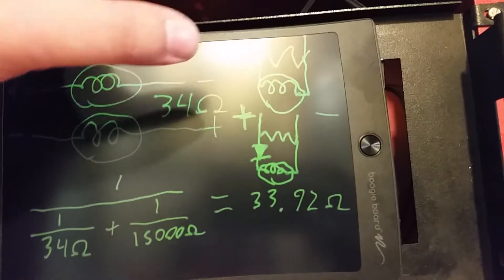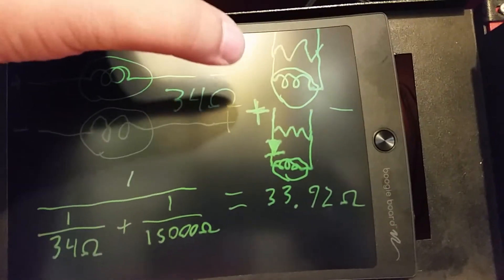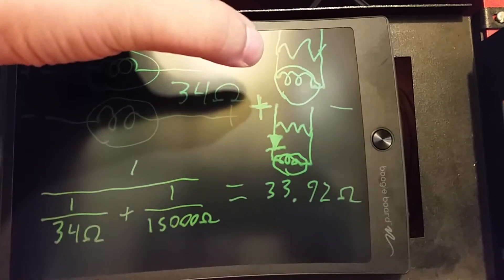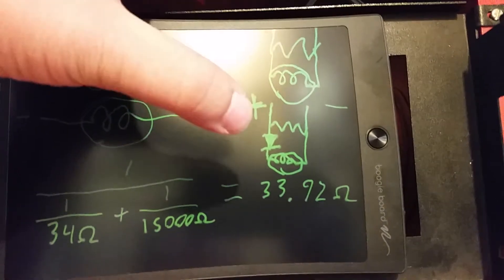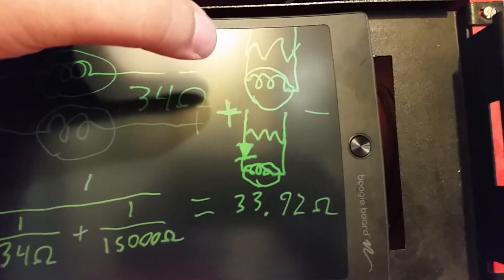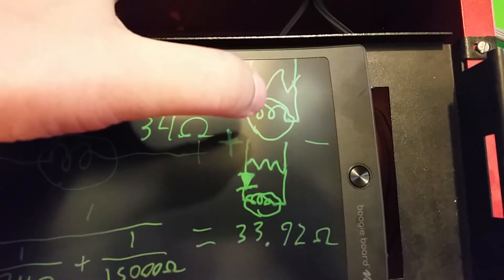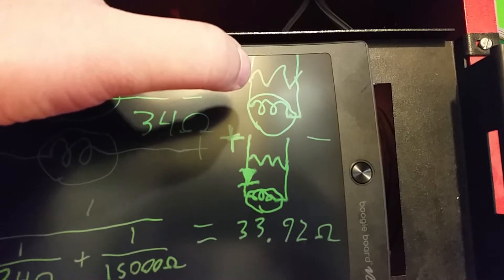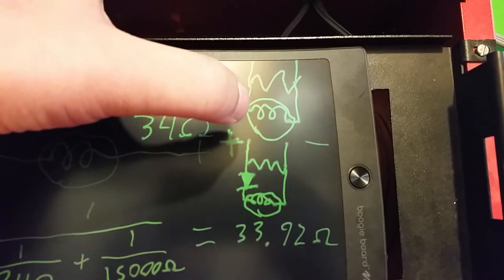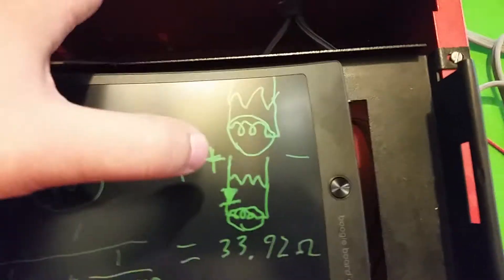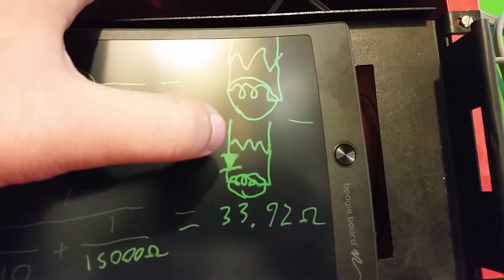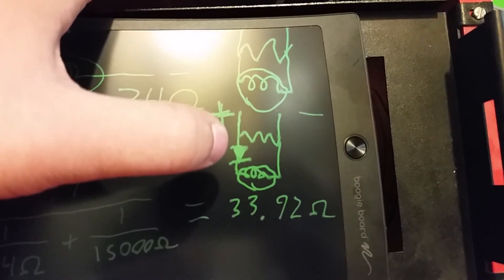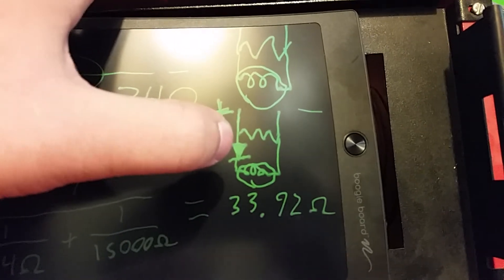Right here, I drew schematics of what the visual circuit would look like at the end. This without the polarizing diode, this with. So here, basically it's two resistors in parallel. You get the end-of-line resistor right here, and you get the light bulb. Here, obviously, is the end-of-line resistor, but you also have the rectifier diode right here to polarize the light bulb.